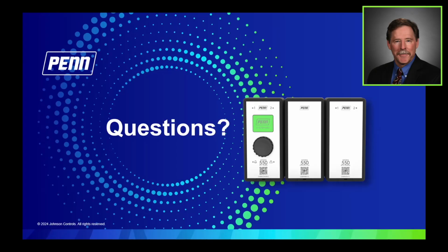And there are plans, matter of fact, we're working on them now, to add another module to this backplane that would allow the data to be ported from that Modbus backplane to a supervisory controller. This is primarily a data dump. It is not allowing that system controller to override any of the functions at all. It will be able to communicate through both BACnet MSTP as well as Modbus RS485 through a user selection protocol. So no special communications in terms of the wireless cloud connectivity. All you need basically is a means to get to the internet.